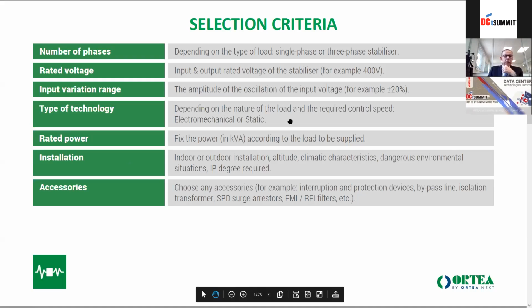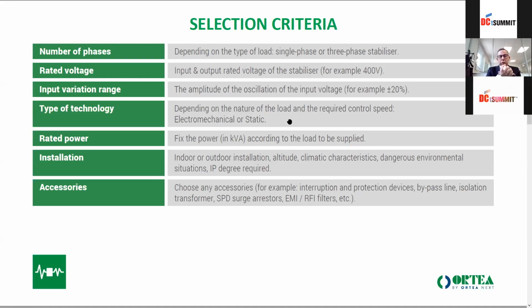The type of technology is linked to how sensitive your load is, so whether it is a load that needs a very quick reaction or not. A normal load will need an electromechanical unit, and a very sensitive load will need a static unit, which has a very, very quick reaction. We will see later in the presentation, for example, that the static is correcting in less than 3 milliseconds, which is a very high speed.